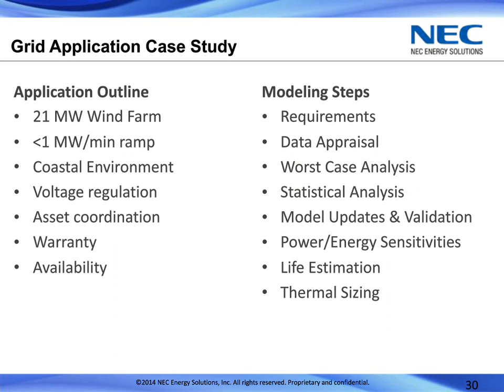So, a basic overview of the case we're looking at. This is a 21 megawatt facility. It has 24 megawatts worth of wind turbines. They're partway around the island though, so there's a fairly long feeder system there. The utility has a 1 megawatt per minute ramp rate, amongst other requirements which we'll talk about later. We're installing in a coastal environment, which introduces its own challenges, none of which are simple engineering challenges. There are also voltage regulation requirements, and we're coordinating other assets on that site.